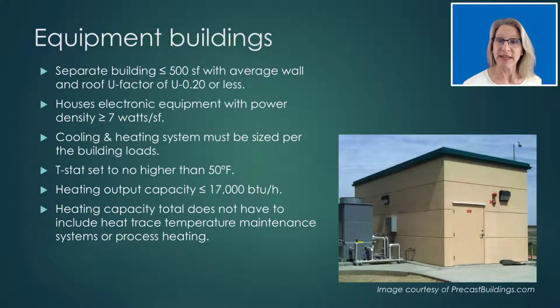The heating capacity limit, which is set at less than 17,000 BTUs, has proven to be an issue for designers wanting to use heat pumps because, due to the high electric equipment power density requirement, the HVAC equipment is sized based on the cooling load. And then for the corresponding heating capacity that comes in the heat pump, there typically isn't a lot of flexibility with capacity, so you kind of get what you get.